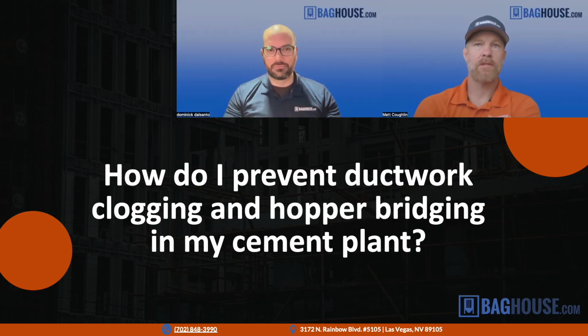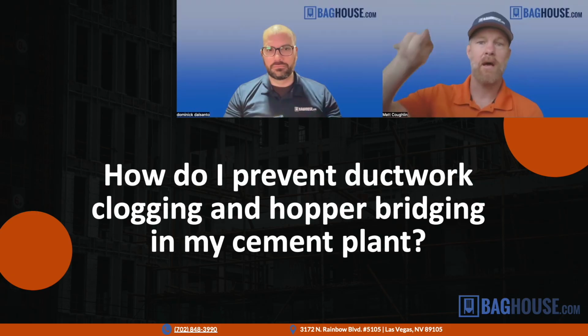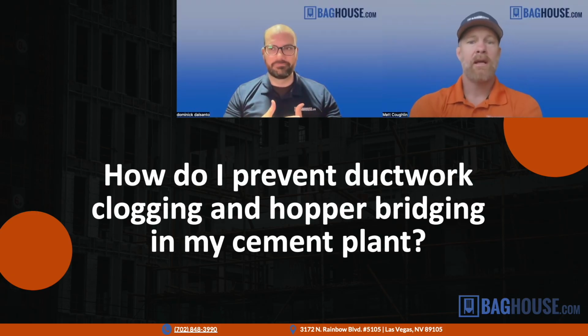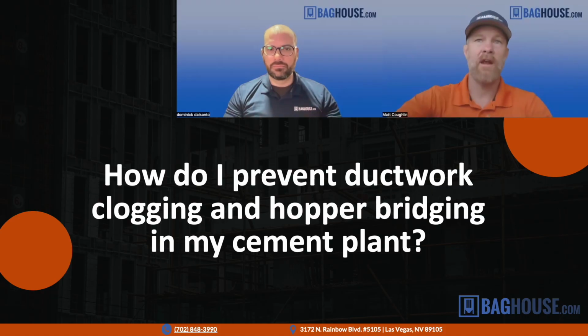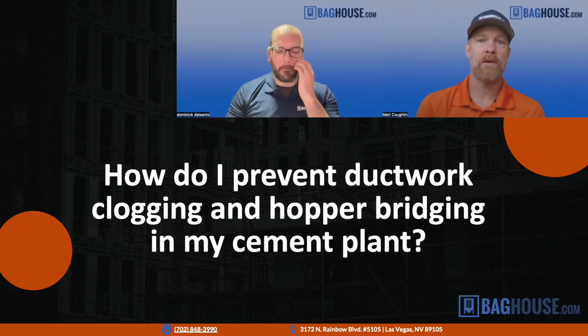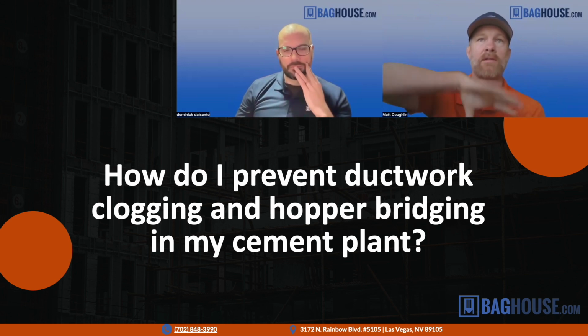Talking about the ductwork, since we're talking cement applications, one thing that's pretty common in crushing, part of the process in particular, you'll see a lot of cement plants have this grasshopper leg style ductwork. And that's pretty common. And the idea there is to basically ensure that the heavier stuff that gets pulled off your conveyor hood falls back into the process while the lighter dust goes up into your ductwork. So you want to make sure that the ductwork itself is sized properly to keep the lighter stuff flowing.